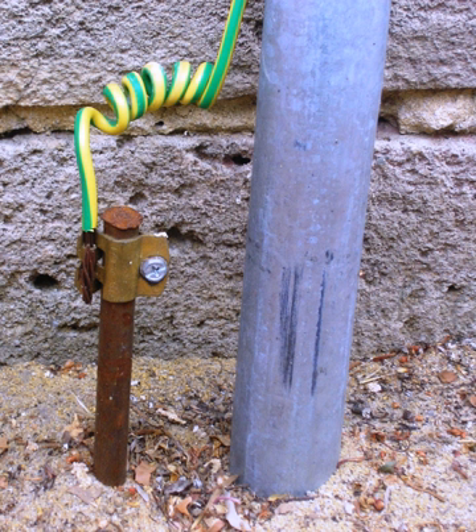Topic: Bonding. Strictly speaking, the terms grounding or earthing are meant to refer to an electrical connection to ground, earth. Bonding is the practice of intentionally electrically connecting metallic items not designed to carry electricity. This brings all the bonded items to the same electrical potential as a protection from electrical shock. The bonded items can then be connected to ground to bring them to earth potential.